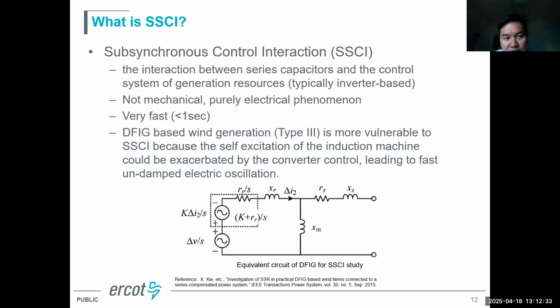The weak grid oscillation, we call sub-synchronous oscillation; the series compensation related one, we call sub-synchronous control interaction (SSCI). It's an interaction between series compensation and the control system of generation resources. It's a purely electrical phenomenon, pretty fast, and typically Type 3 or doubly-fed wind machines are more vulnerable to SSCI because of the induction generator effect.